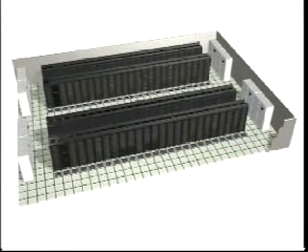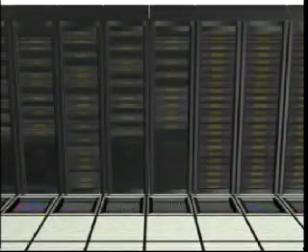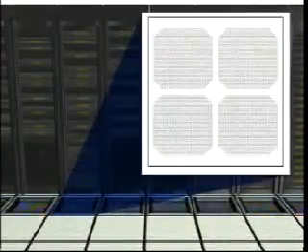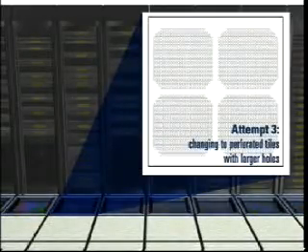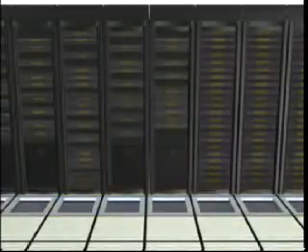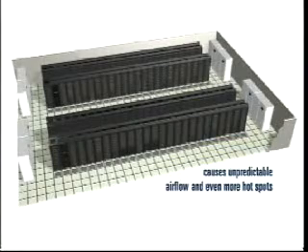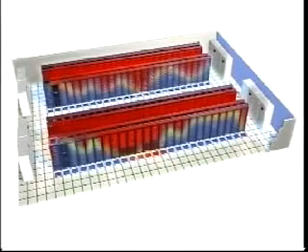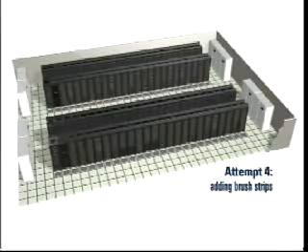The data center manager tries to deal with the problem by replacing the tiles. To make perforated holes larger, he changes out some of the standard floor tiles with 56% free perforated tiles. This causes a drop in air pressure and non-uniform airflow that, in turn, creates unpredictable airflow patterns. Even more hotspots form due to the reduction of airflow in some areas. The data center manager tries plugging up cable access holes with brush strips. Unfortunately, this only has a slight impact on the problem.